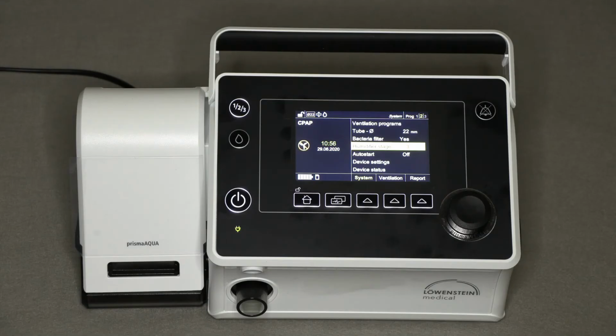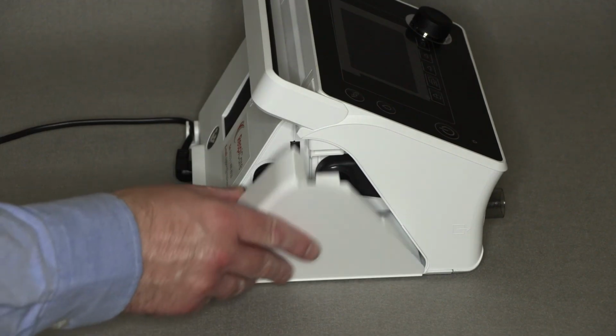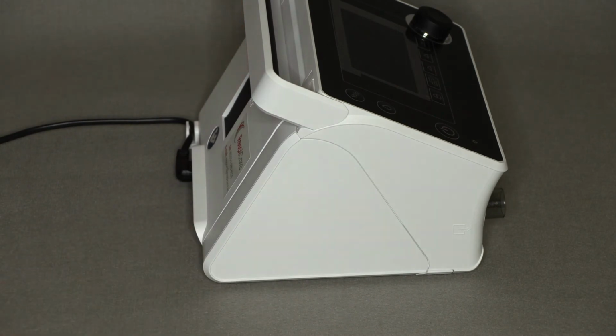To remove the humidifier for refilling, simply press the large button at the rear of the ventilator and the humidifier will disconnect. Heat will not be applied to Prisma Aqua when the ventilator is running on battery. This is to save on battery life. So if the ventilator will be used in transit or if a humidifier isn't required, just fix the ventilator side door back in place.